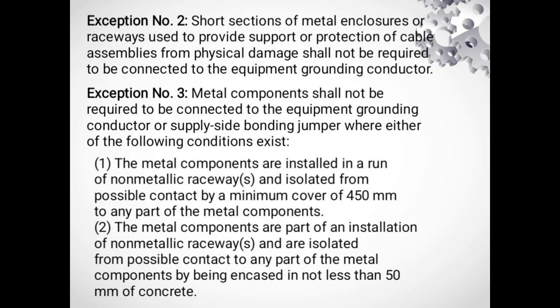However, it's crucial to be aware of the exemptions outlined in section 250.4. Exception number 2 permits the omission of an EGC connection for short sections of metal enclosure used solely for physical protection. Exception number 3 addresses metal components within a non-metallic raceway, provided specific isolation conditions are met. These exceptions are narrowly defined and should be applied with careful consideration.